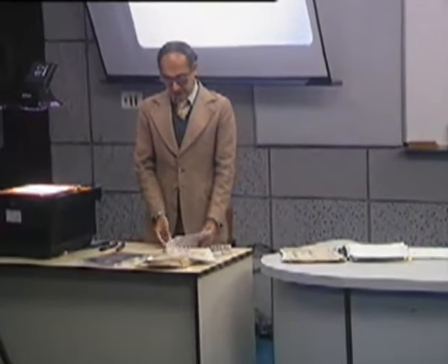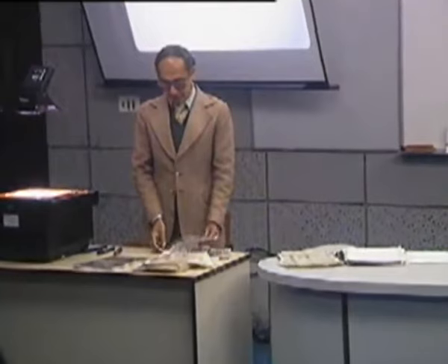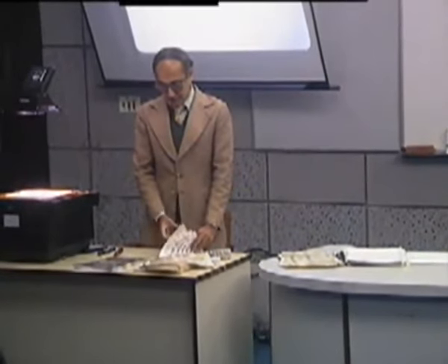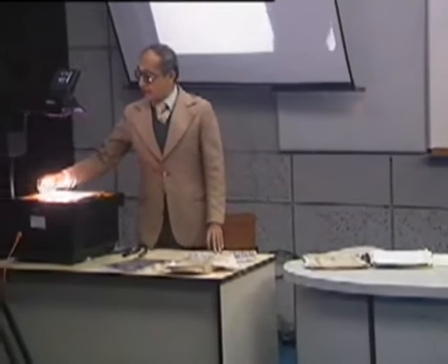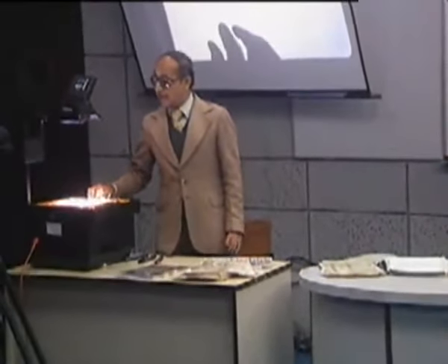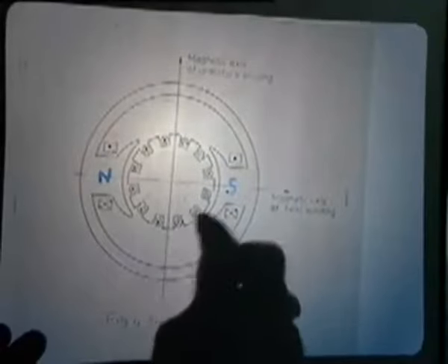So we call that what is known as armature reaction. We have seen that normally flux is produced like this, but once the armature also starts carrying a current, that will also produce a flux in this direction. Whenever the armature is carrying current, it is likely to change the natural flux pattern of the air gap. Therefore, that phenomenon we call armature reaction.